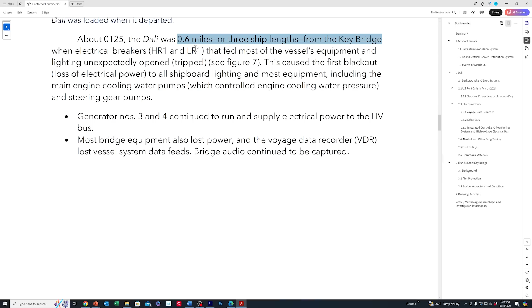At 1:25 in the morning, the Dali was 0.6 miles, or 3 ship lengths, away from the Key Bridge when the electrical breakers HR1 and LR1, which feed most of the vessel's equipment and lighting, unexpectedly opened and tripped. These are the two that tripped right here, HR1 and LR1. Both of them went open on us.